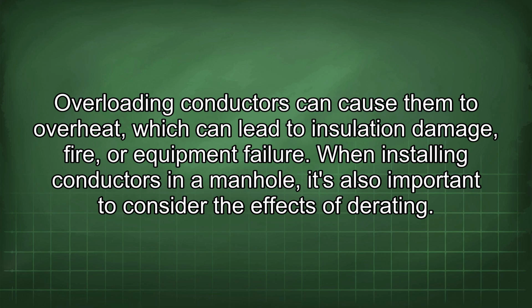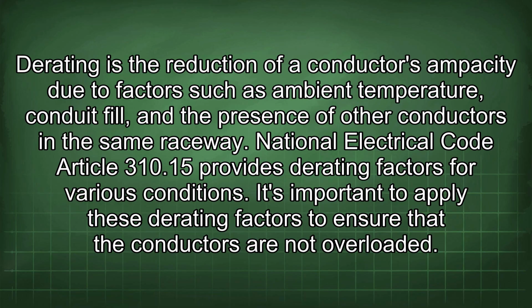When installing conductors in a manhole, it's also important to consider the effects of derating. Derating is the reduction of a conductor's ampacity due to factors such as ambient temperature, conduit fill, and the presence of other conductors in the same raceway. National Electrical Code Article 310.15 provides derating factors for various conditions. It's important to apply these derating factors to ensure that the conductors are not overloaded.